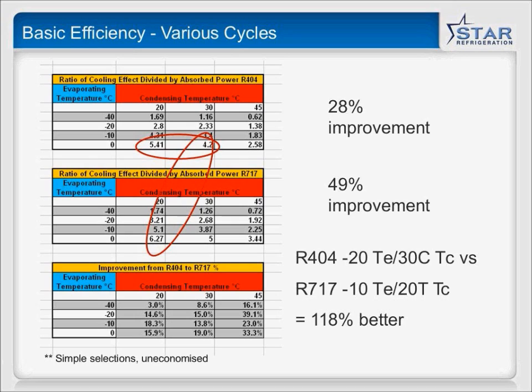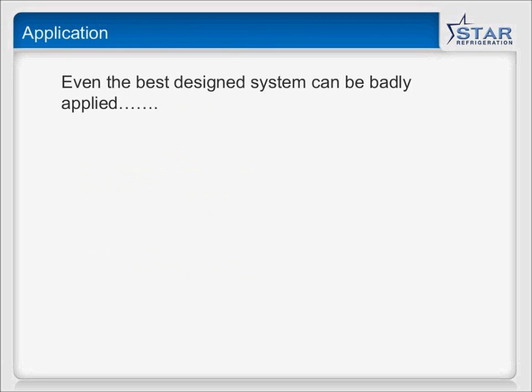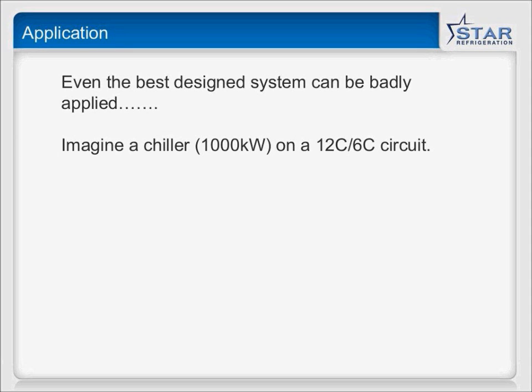Thinking of a particular example here, supposing we've got a chiller that's 1,000 kilowatts and we're doing 12/6 cooling, but in springtime we've got lower air conditioning requirements, so it's only running half loaded. The classic thing that somebody would want to do is fit an inverter onto the glycol pump, push less glycol around the system because the glycol pump consumes a lot of electricity. I always think it's a very simple rule of thumb: aim for the biggest motor and work there first.